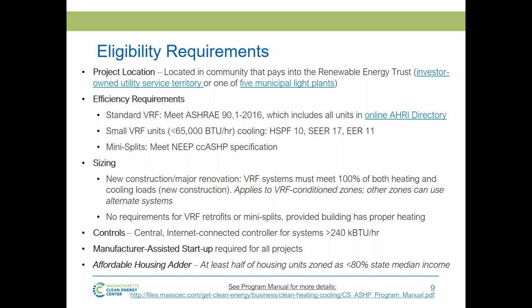In terms of sizing requirements, this is just a requirement for new buildings participating in the VRF program. We don't have a requirement for mini splits or for retrofits, but VRF systems need to meet 100% of both the heating and cooling load for new construction. That applies to the zones that are conditioned by the VRF system. So if there are, say, hallways or hard to reach areas where it's a relatively minor ventilation load, or a relatively minor portion of the load, those portions of the building are exempt. But for the most part, we want to make sure that it is meeting the full heating and cooling load.